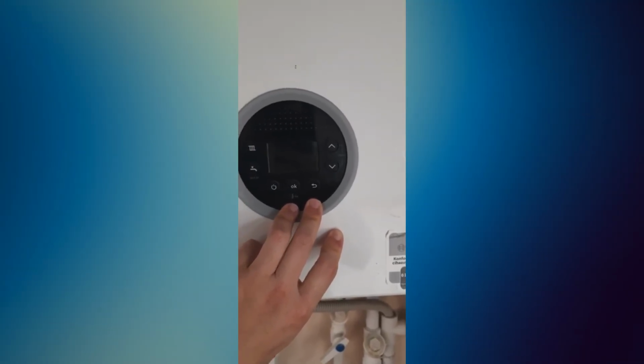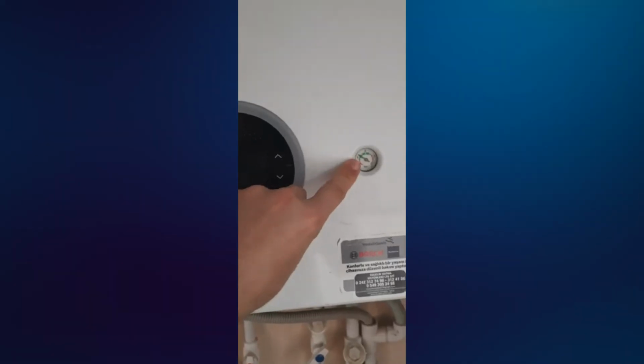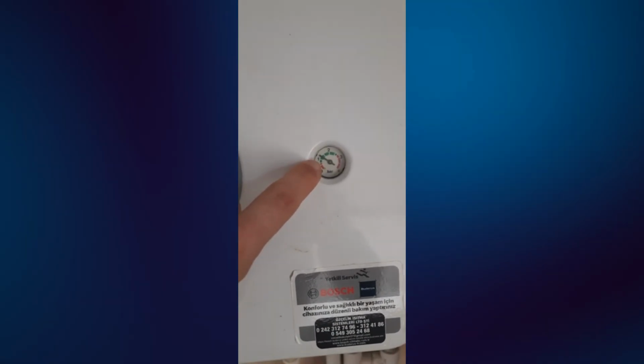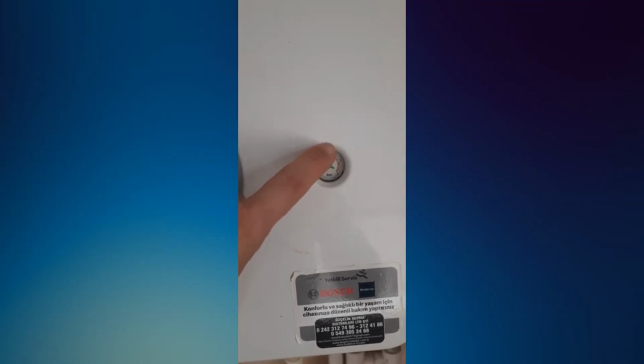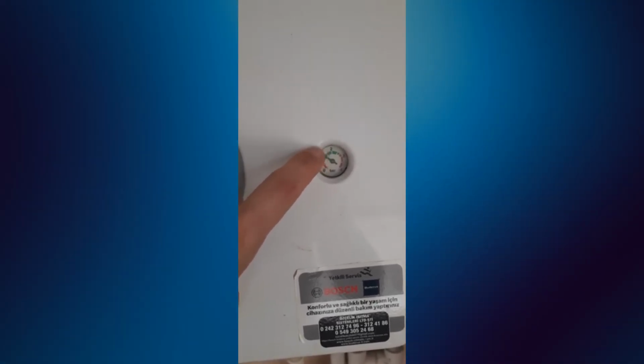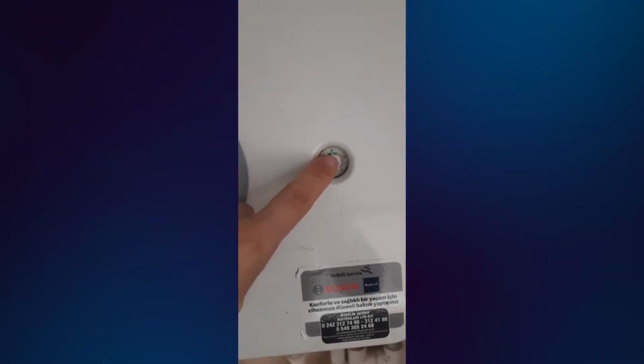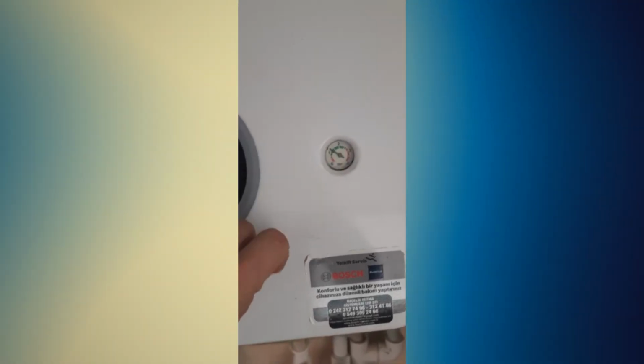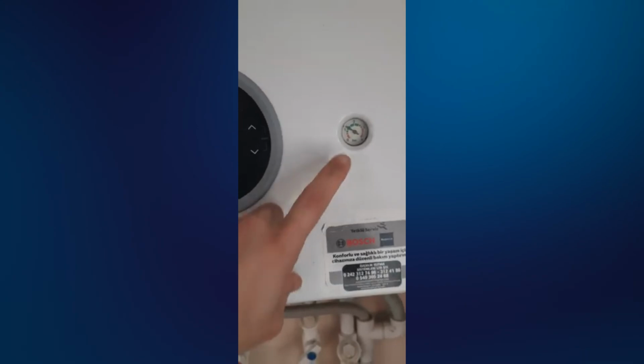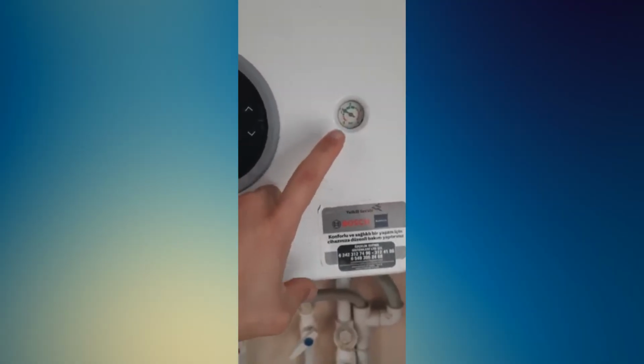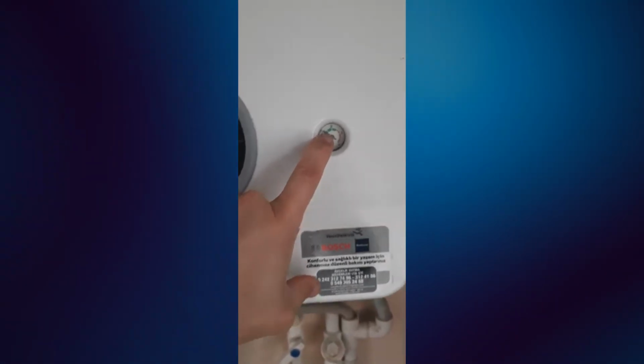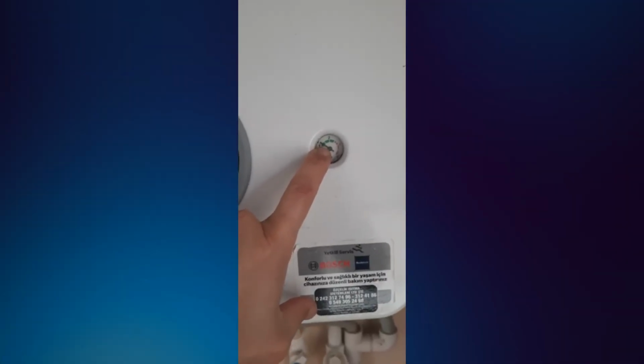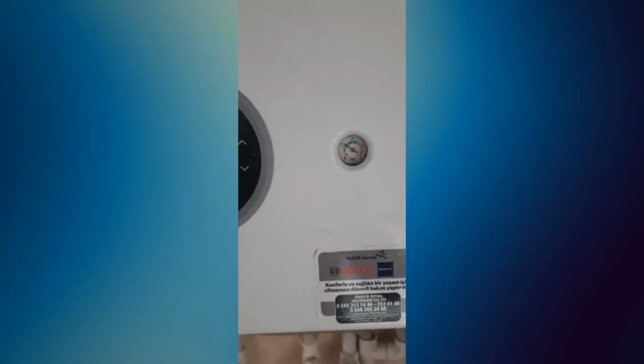The ninth possible cause is wiring, sensor, or control board failure. If the flame sensor, ignition system, gas valve, fan, condensate system, pressure readings and combustion setup all check out, then the control board or wiring may be involved. This is usually diagnosed after the more common causes have been checked, because replacing a board without testing can be expensive and may not fix the fault.